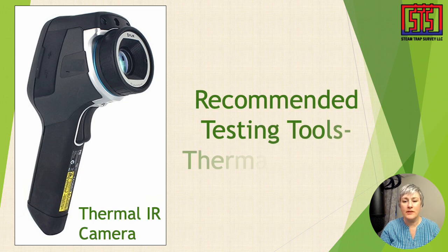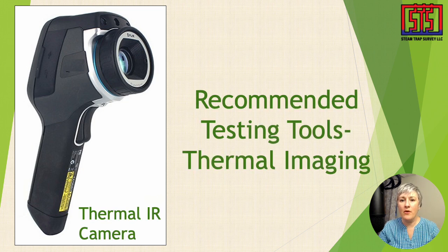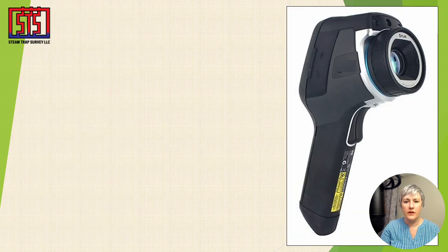Recommended testing tools: thermal imaging. The amount of radiation emitted by a steam trap increases with temperature. Therefore, thermography allows one to see variations in temperature. When viewed through a thermal imaging camera, a failed open trap may become easier to detect.